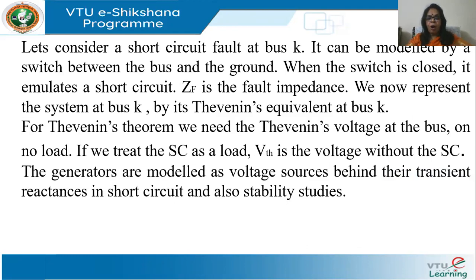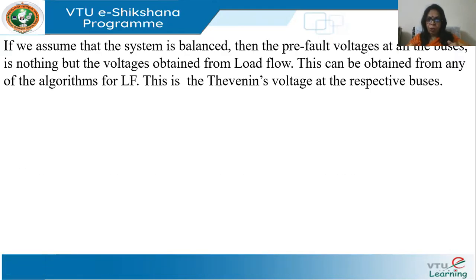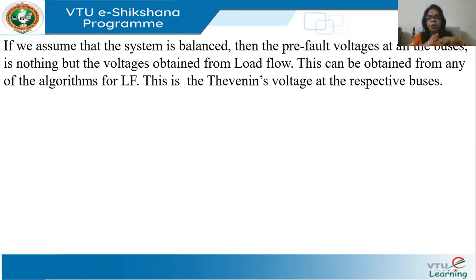In this model, I'll model the generators as voltage sources behind their transient reactance, as used in short circuit and stability studies. The voltage at the bus without the short circuit is obtained from load flow studies. When you do the load flow study, you have the entire network, the given generations, the given loads, and you solve for the network voltages — there is no short circuit anywhere. So from a circuit viewpoint, I can treat all these bus voltages as the required Thevenin's voltage.